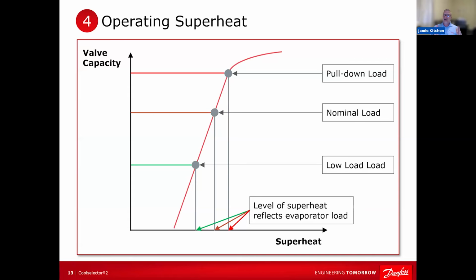So what happens is that TXV is going to open up and it's going to feed that evaporator as much refrigerant as that compressor can take, right? And your evaporator pressure is going to go up. Your saturation temperature is going to go up. Because if you have a fixed speed compressor, what's the only way to put more refrigerant through it? And that is for the density of the refrigerant to increase in your suction line. So your pressure and temperature need to go up.